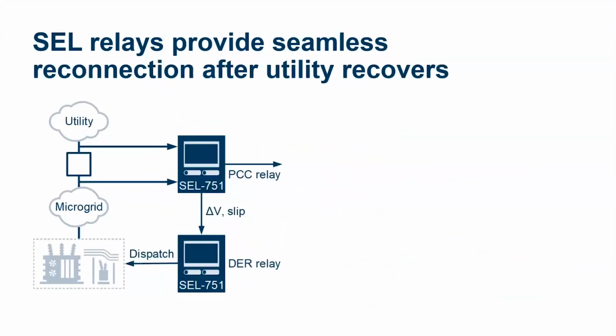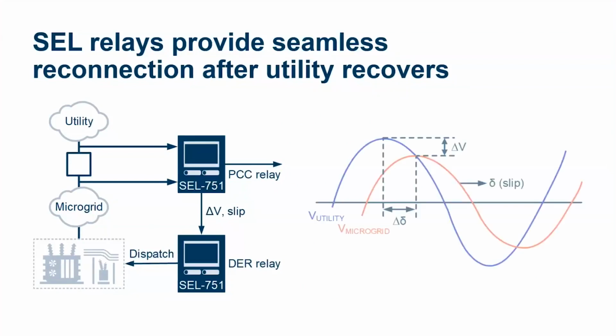We also provide seamless reconnection. When a utility fails and you've islanded, you need to reconnect. You can't just close a breaker. You could damage equipment and need to replace it. So we use a relay at the point of common coupling to measure the voltage amplitude difference and the frequency difference, called slip, and then send a dispatch to relays attached to every engine, battery, and even photovoltaics. We measure these parameters at the point of coupling, and the dispatch looks like this.